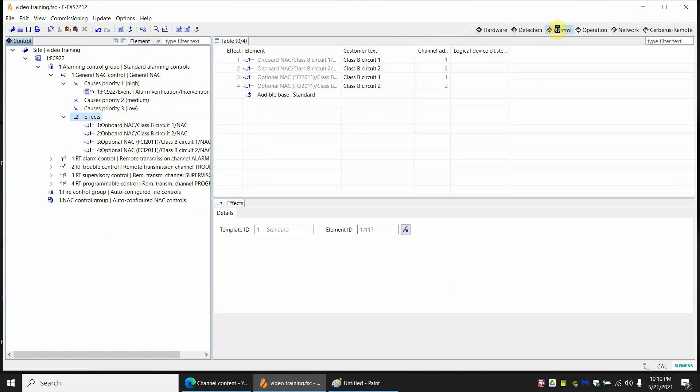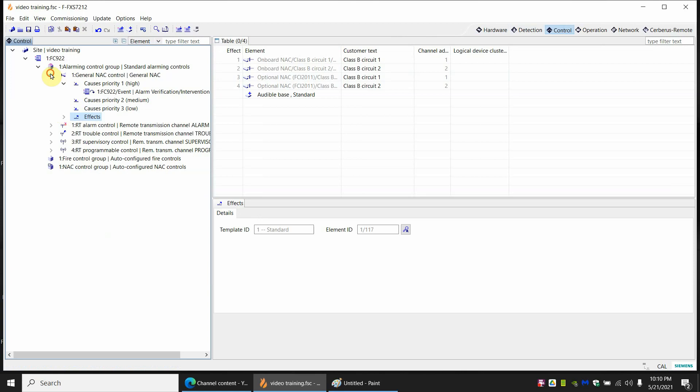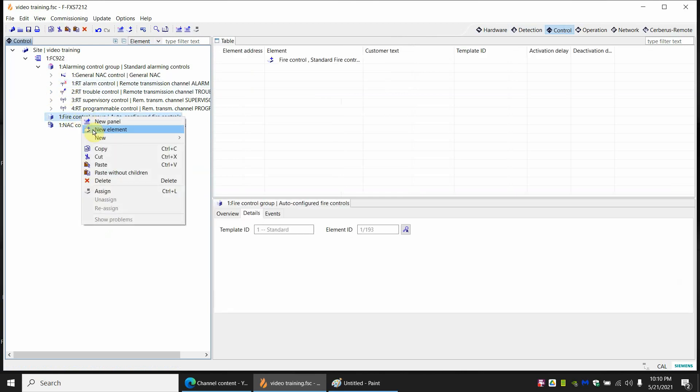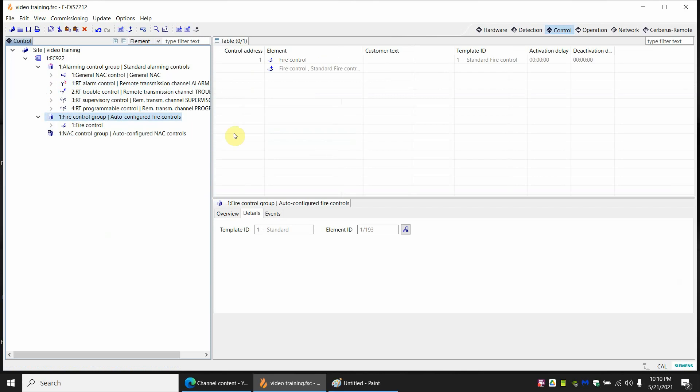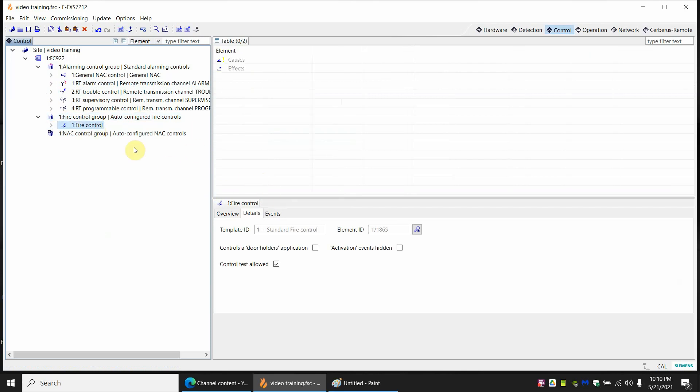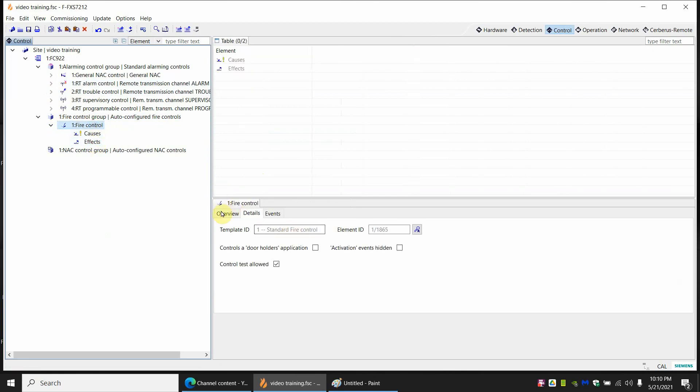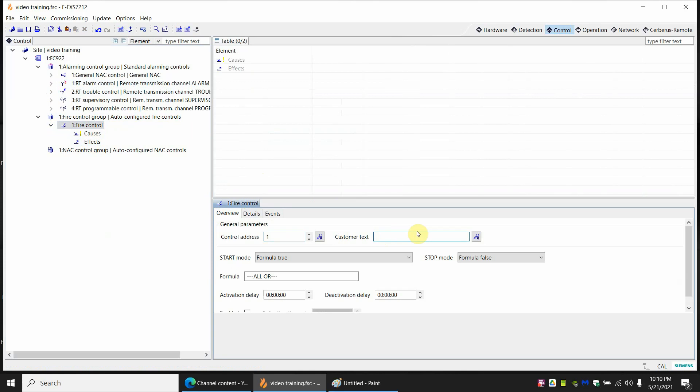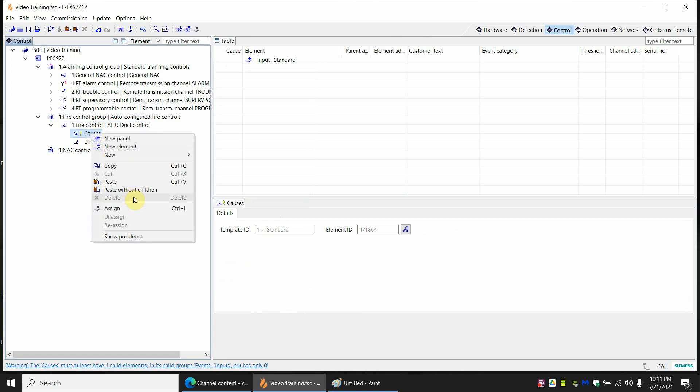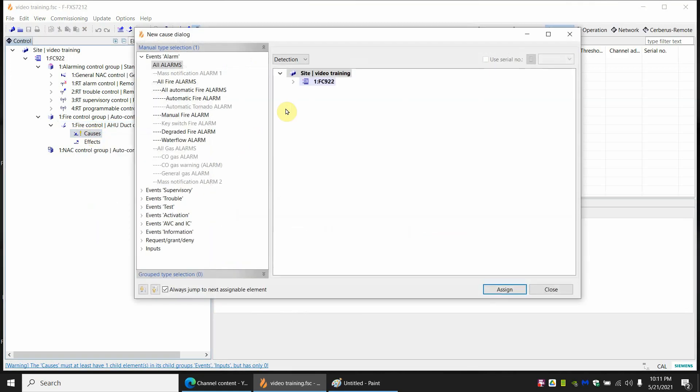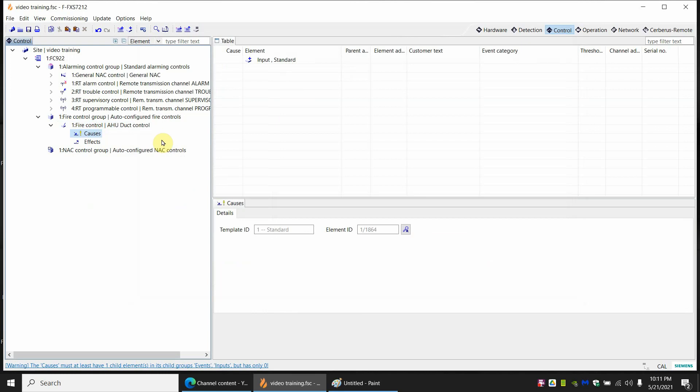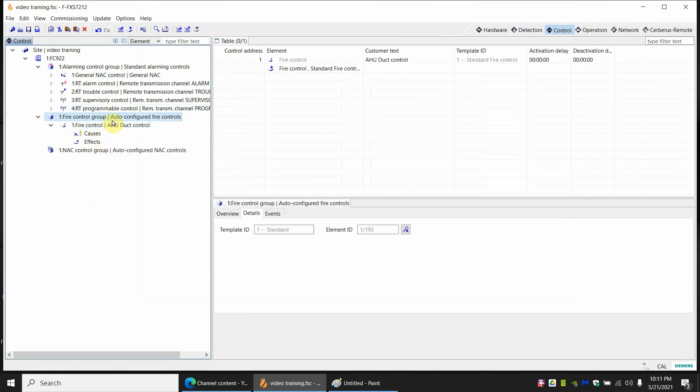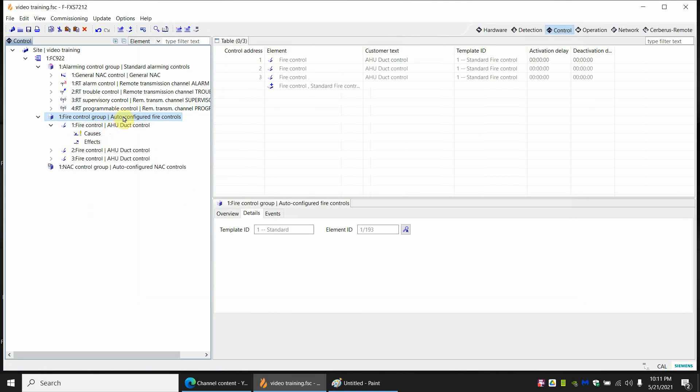So we're going to go to control. And you've got the fire control group. And we're going to make a new fire control. Just a standard fire control. And the basics of what you would do here is you'd have a cause and effect. And for the most basic cause and effect it's an OR command. So if any one thing happens in the cause, the effects have to happen. So we're going to call this control customer text we're going to call this air handler duct control. Before we do that actually I will make four copies of this before sticking anything in there. So over here I'm going to control on the fire control. And then on the group I'm going to paste it three more times.